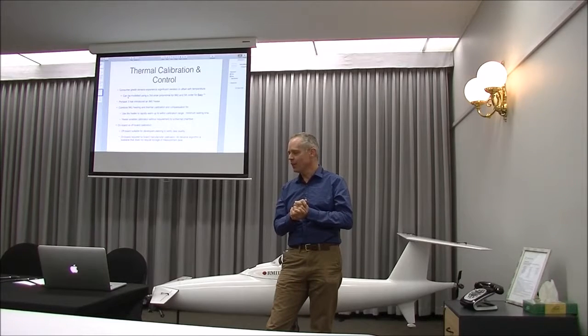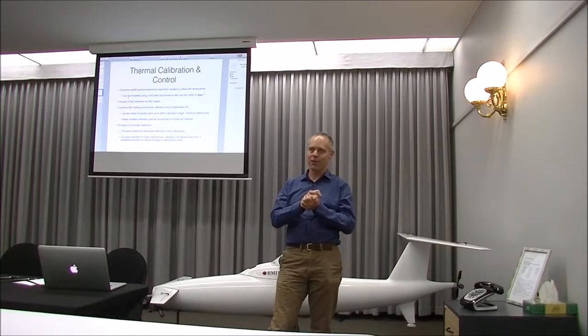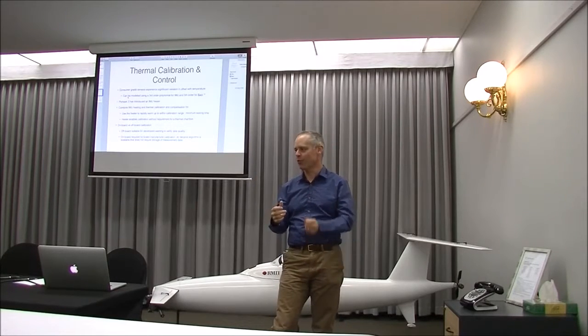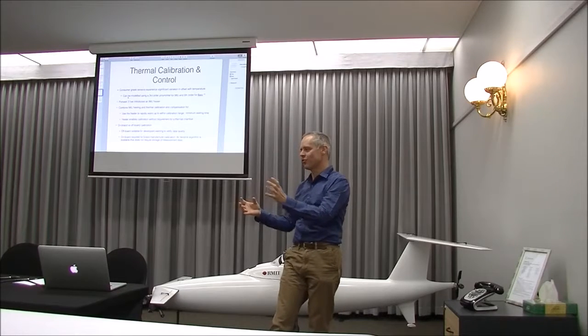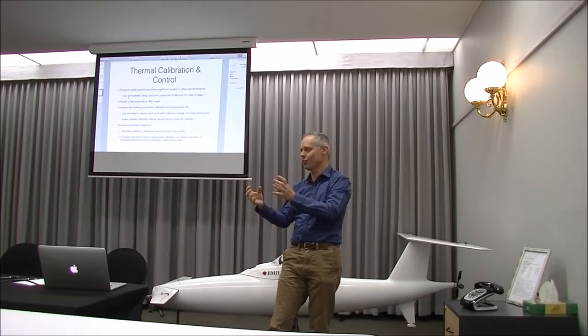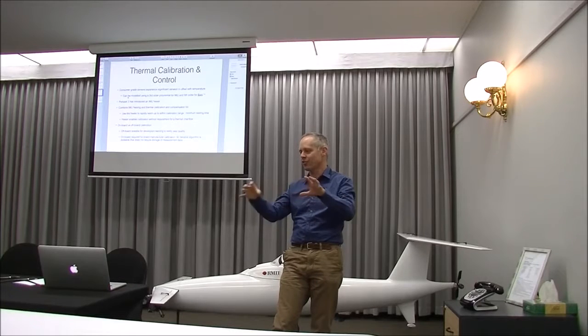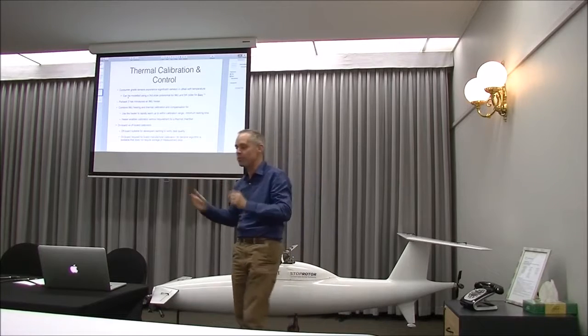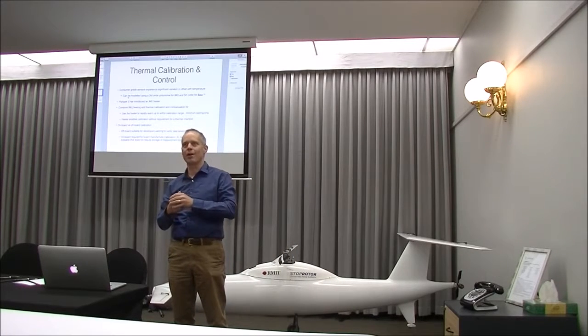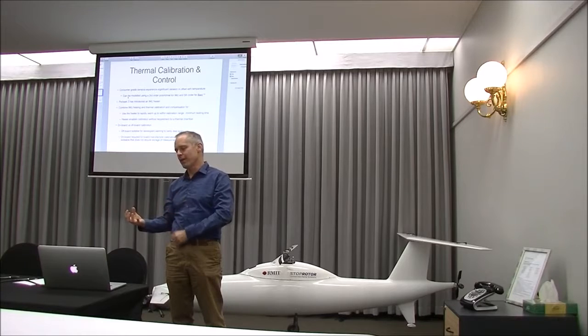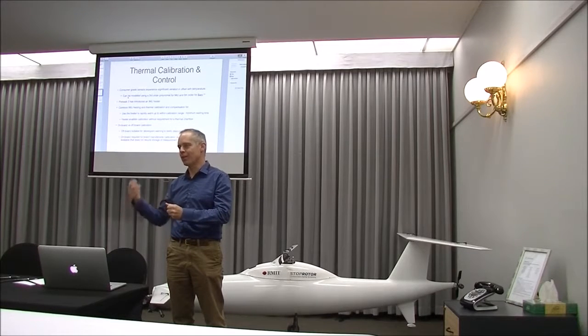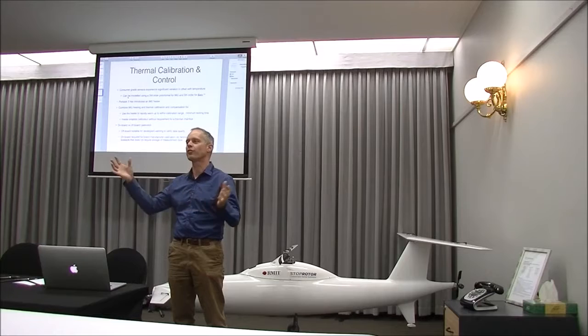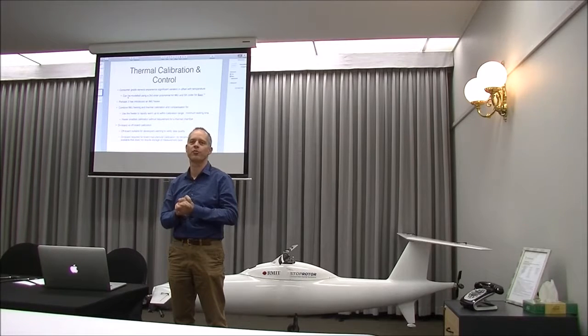On the other hand, if you want to calibrate a bunch of these, maybe a factory decides to offer a calibration certificate and environmental testing to users willing to pay more for that additional processing. Then they want something where it comes off the line, goes into the thermal chamber, gets power applied, automatically self-calibrates, saves the coefficients, and provides an indicator that it's successfully completed.